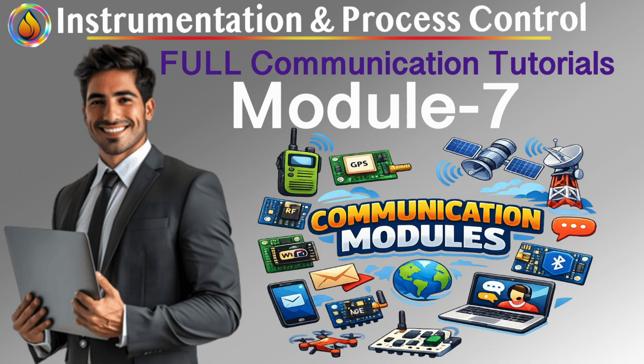Link master: I can keep time if needed. A link master is a more capable device. Examples include controllers, advanced field devices, and interfaces with higher intelligence. A link master understands the schedule, can become the LAS, can issue control messages, and can maintain network timing. But here's the subtle point. "A link master is eligible to be LAS, not always the LAS." This allows redundancy. If the active scheduler fails, another link master can take over. The bus doesn't collapse just because one device disappears. This is fault tolerance by role design.